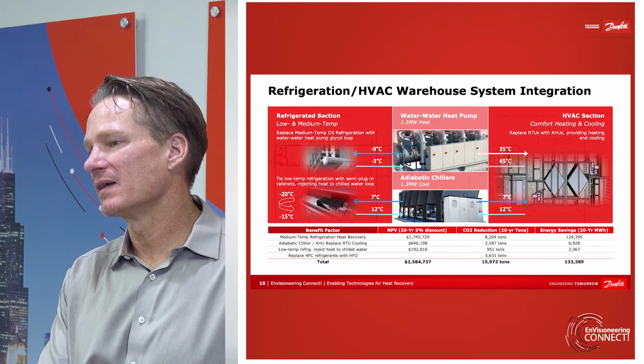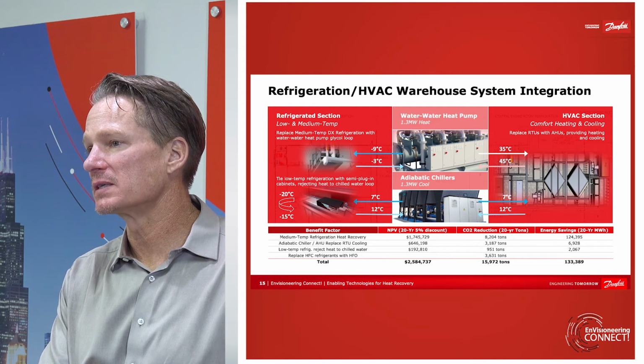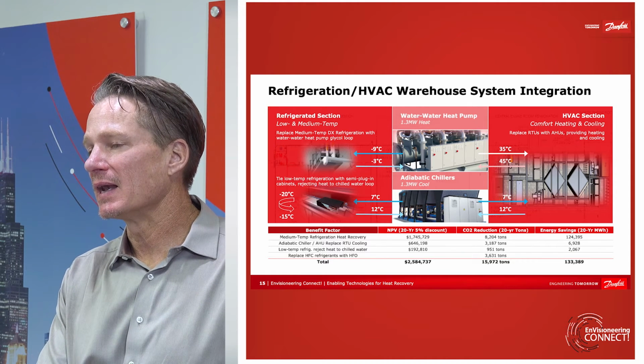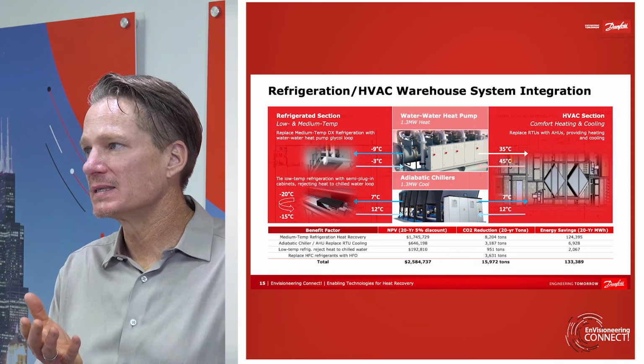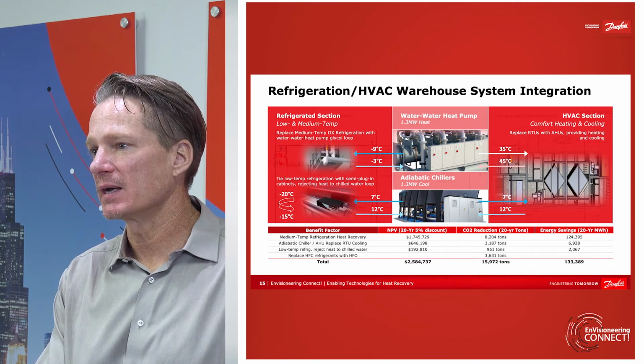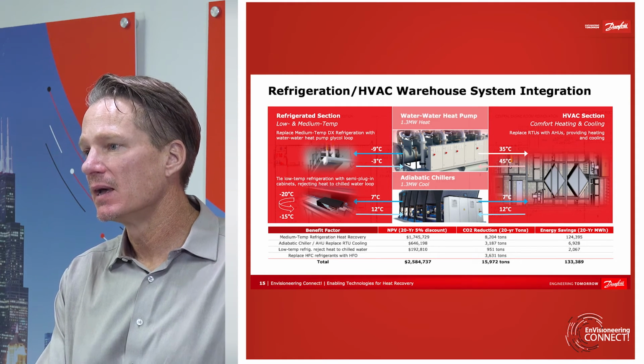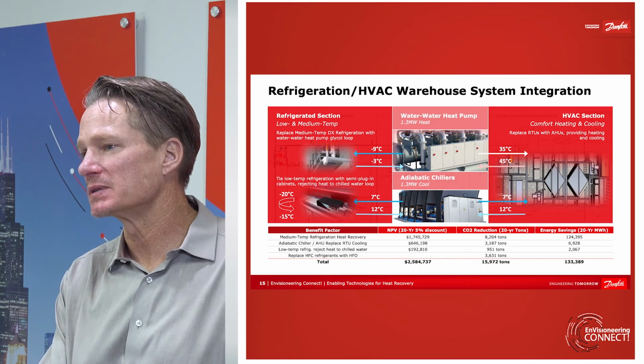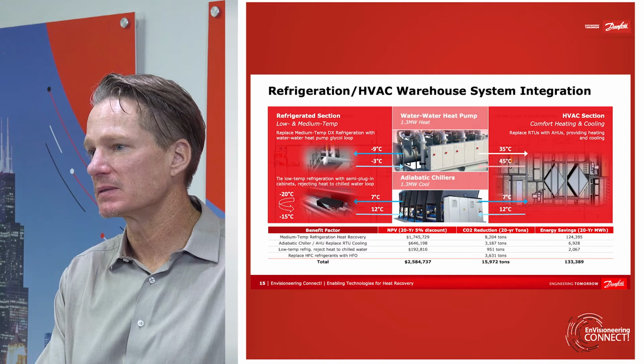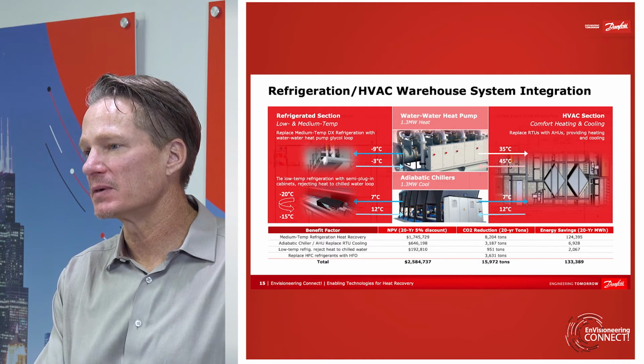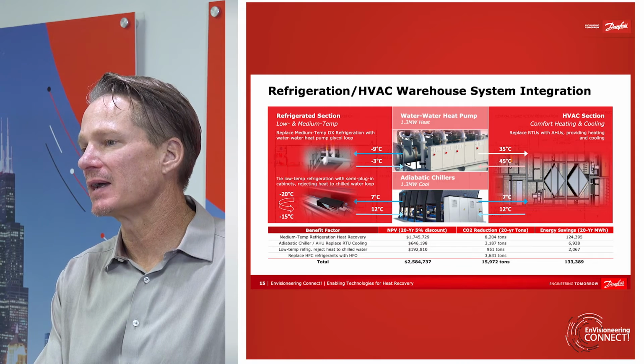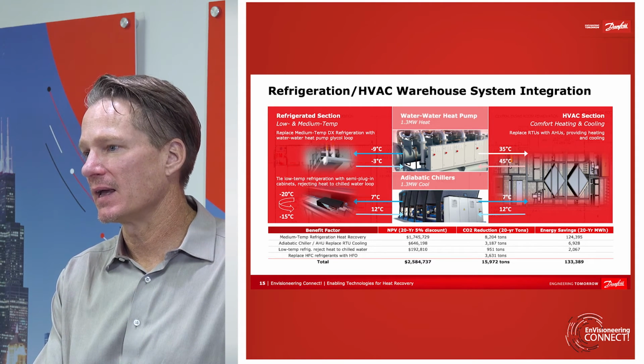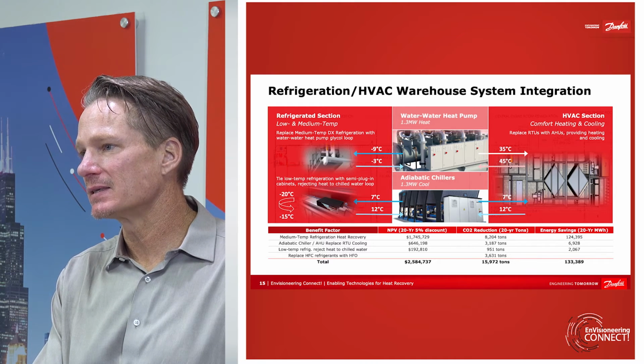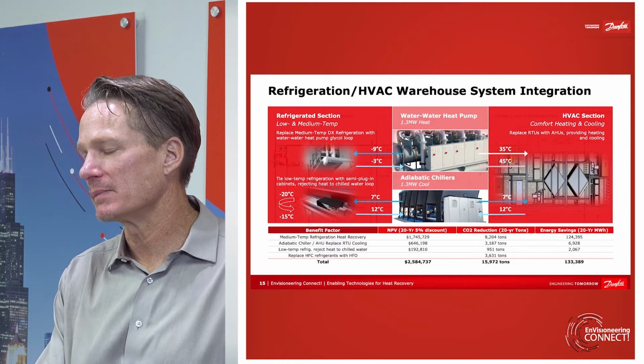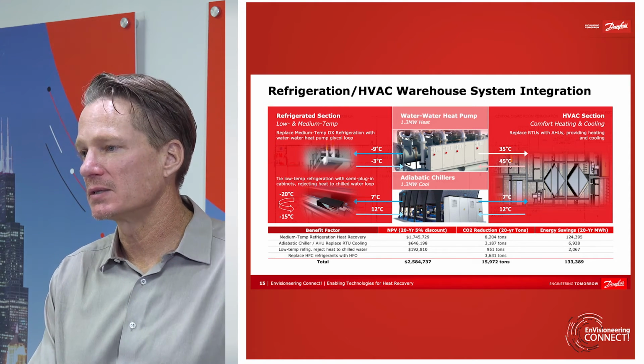Another application that we've been working on is systems integration of a large refrigeration and HVAC warehouse. And how we did this is pretty interesting because these systems are another example of a harder system to electrify. Tying in a refrigeration system to the HVAC system is a tough thing to accomplish because of the disconnect between those two systems, or the historic disconnect between those two systems. But how we did this was integrating in the medium temp refrigeration system and tying that into a water-to-water heat pump, and then taking the low temp refrigeration system and tying it into the chilled water system via an adiabatic chiller. That then supplies the heat to the air handling units that replace the rooftop units that were formerly used to cool and heat the rest of the warehouse.